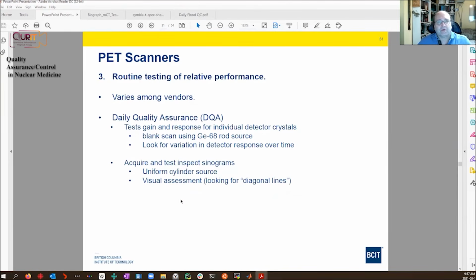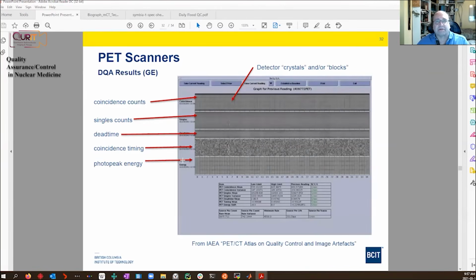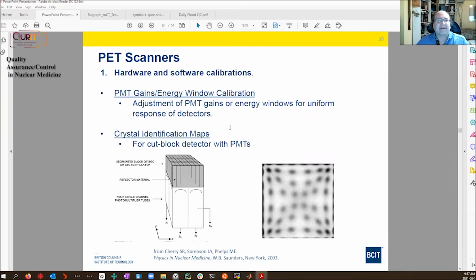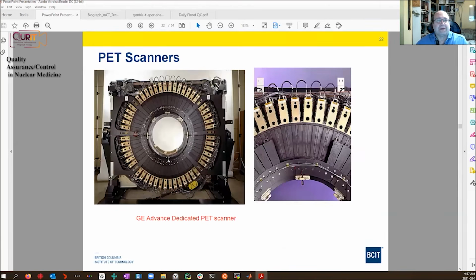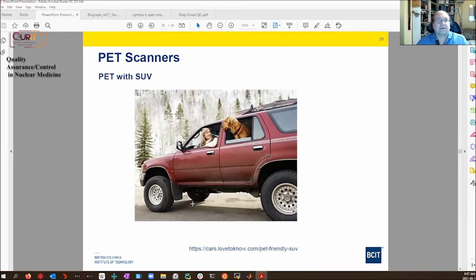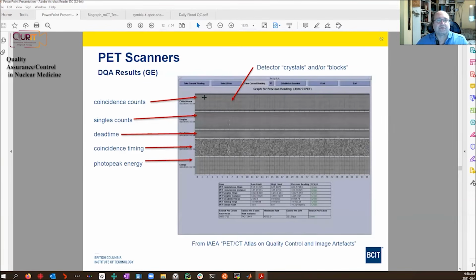Quality control, relative testing, routine testing of relative performance. Again, these vary with the vendors. GE has this daily quality assurance where they uniformly irradiate the detectors. So if we go back here and we take this ring and we cut it here and we unroll it so that it is a flat rectangle, that's what we see here. So these are the different detector blocks and the individual detectors in here.